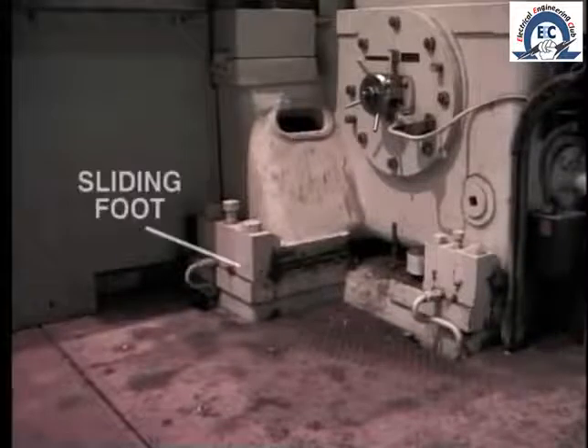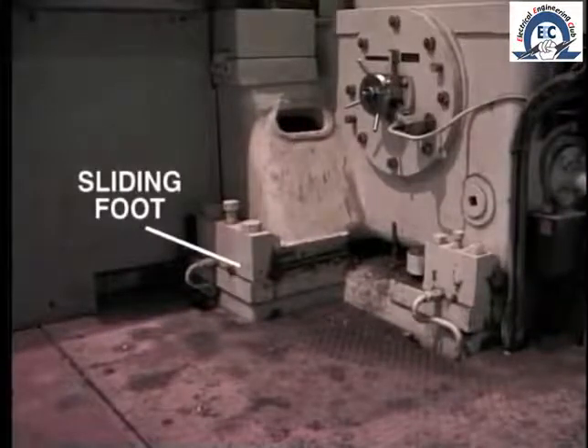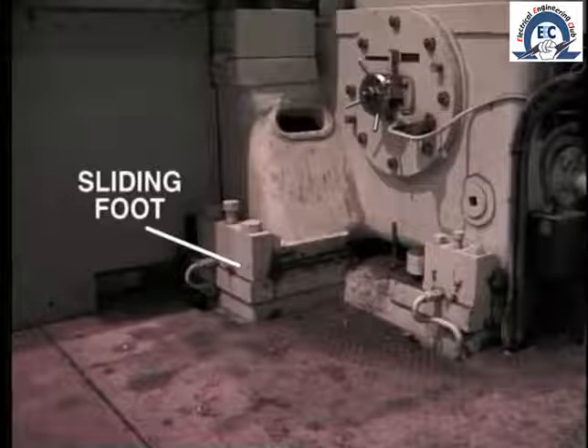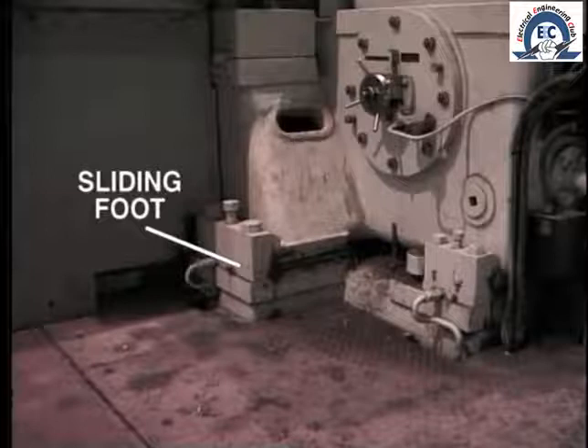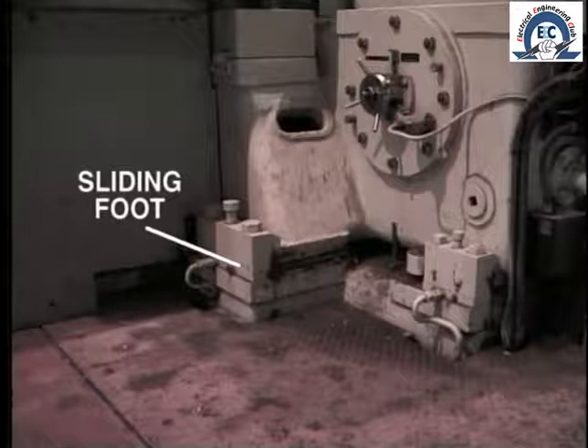In this case, the rotor contracts much more rapidly than the shell, and as a consequence will reduce the differential expansion and generally move into the negative zone. Normally, the manufacturer sets limits of differential expansion for both the negative and positive sides. The expansion position of the governor pedestal is also indicated. After a short overnight shutdown, it is probable that the turbine shell will still be considerably expanded, while the rotor has contracted to provide a negative differential. This indicates that a hot start is required.